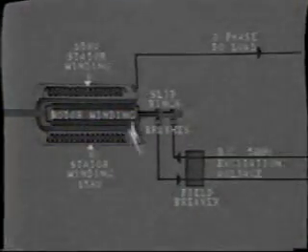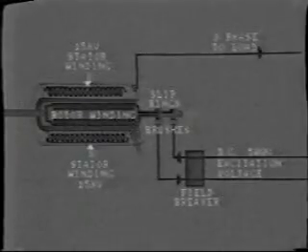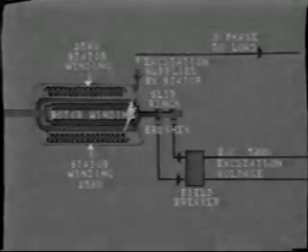For this reason, a ground fault on the rotor will not call for immediate tripping, but rather the need to schedule a convenient outage for inspection of the generator. We'll be looking at rotor ground detection later in this tape. Yet another internal fault could cause the failure of excitation altogether. This could provide a serious upset to the power system as it attempts to supply the excitation current through the stator windings. We'll be talking about this and other faults in more detail later in this tape.